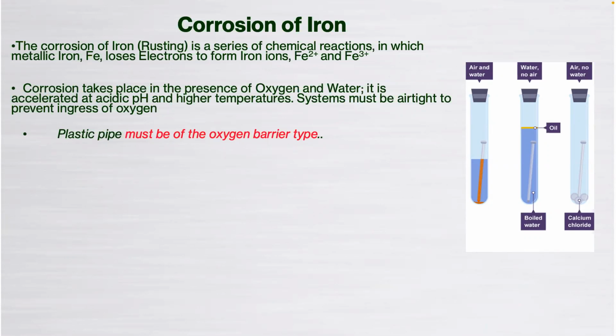If you are using plastic pipework within your system, we want to again prevent oxygen from entering the system. There has been in the UK, I'm not so sure of any, I've not heard of any anecdotal stories in the US, but if you are using any kind of plastic in your system, certainly pipework, just make sure it's of the oxygen barrier type. We had for years an issue here in the UK where pipework was allowing oxygen in through the pipe wall, and then radiators were lasting literally a matter of months.